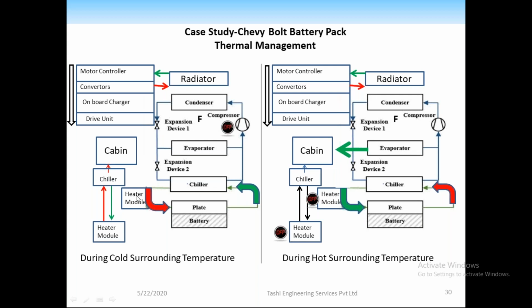Instead, the heater module is on, and there's a pump - which I haven't mentioned in this diagram since it would add too many details. There's always a pump to circulate the refrigerant and the water-ethylene glycol mixture through the chiller. The pump moves the water, which takes heat from the heater, turns hot, and that hot liquid is input into the plate and then goes into the chiller. This is the cycle, so my battery cold plate is kept warm in this condition by putting the heater in the on position.